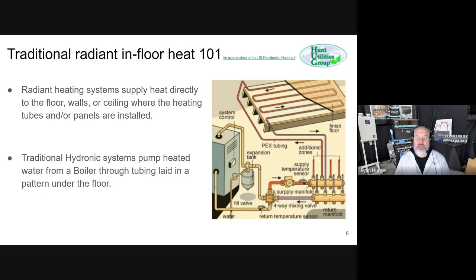So the traditional system, you've got loops in the floor, you run hot water through it, it warms your floor. Pretty simple. Those connect to manifolds. You have to feed all the loops, and there are pumps to do that. The heat comes from a boiler. There's an expansion tank because as you heat the water up, it expands and you have to allow for that. Otherwise, it'll generate very high pressures. You also have to be able to take bubbles out, so you have to have a bubble remover. And if the system gets low, you've got a fill valve. There are a lot of little details here to make that work.